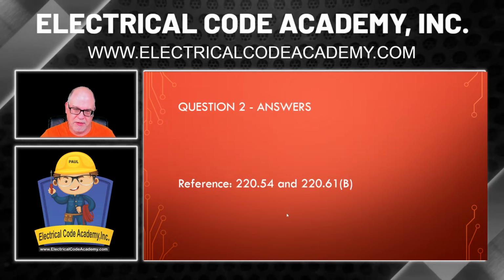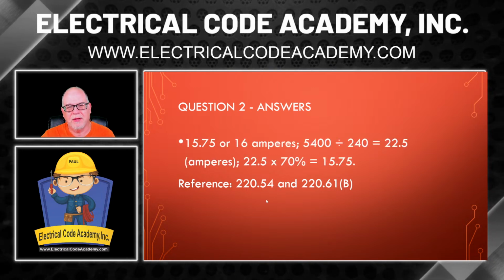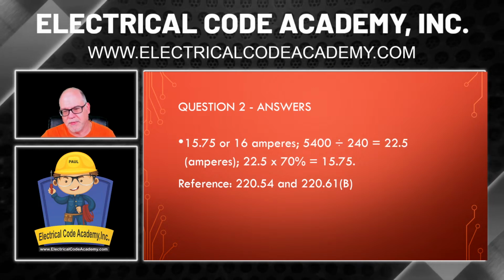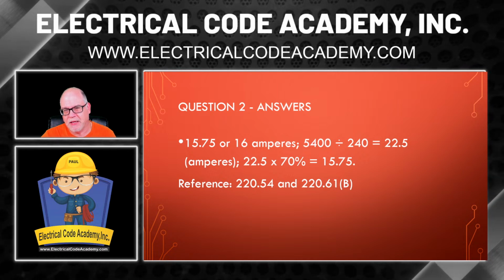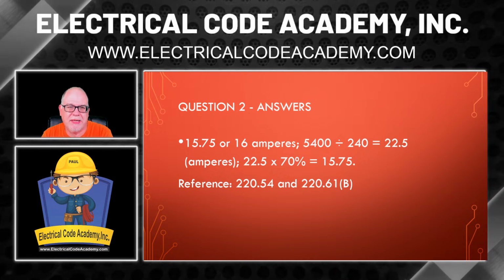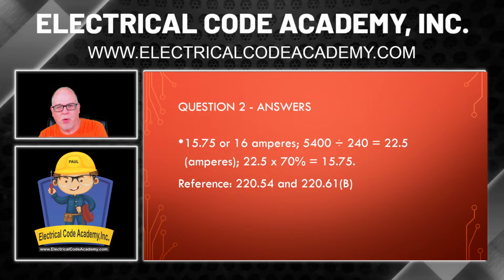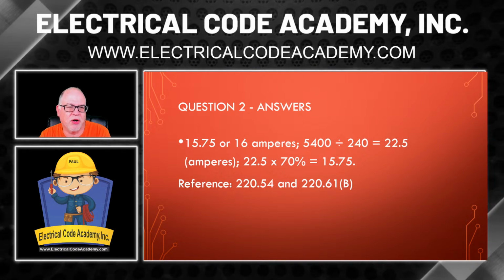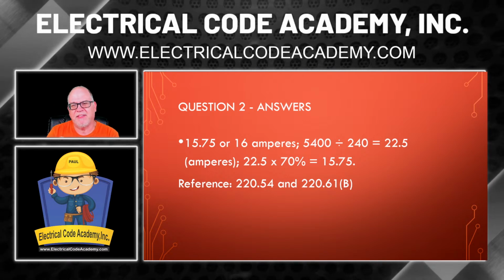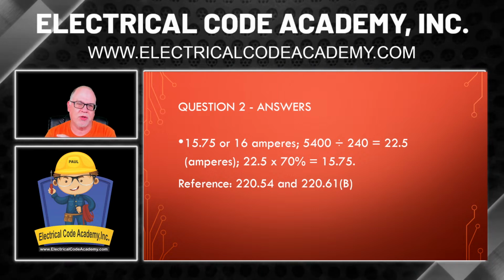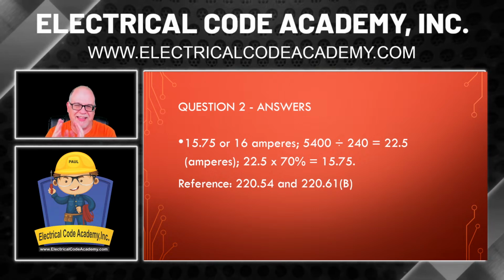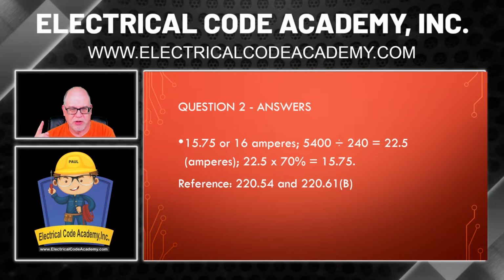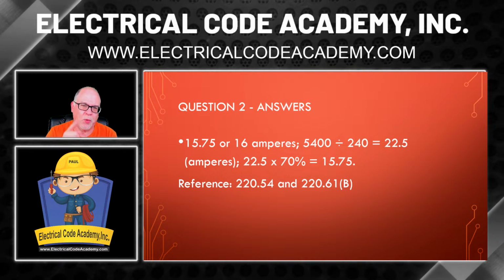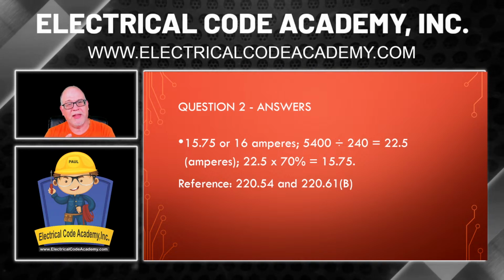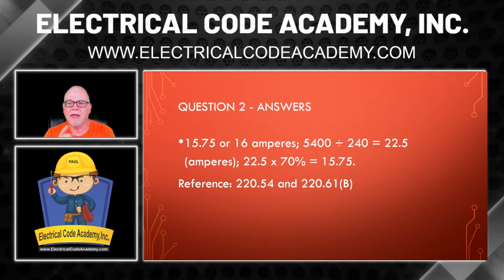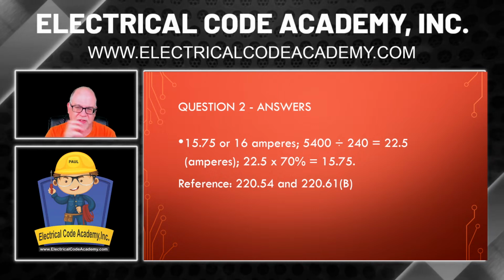And we know there's a code reference. And there you go. As you can see here, it's simply 5,400 divided by 240 is 22.5. We did that earlier. But we multiply that by 70%, or as I always like to do, I would like to convert this to a decimal. So I take that 70%, go from the right, move it two spaces to the left, so it's 0.70. You learn all that kind of stuff in our program, and that means you're working decimal values.